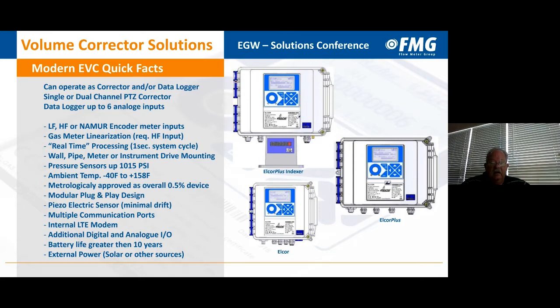Overall accuracy with the chart recorders, you were lucky to get 2% accuracy. Now you're looking at 0.5% accuracy, just using the electronics and doing real-time reads. In some of the older chart recorders, and yes, I'm guilty of selling some of them, I won't mention any manufacturers' names, but I sold a manufacturer that was only good to -10 degrees Fahrenheit. Today's electronic instruments, this one included, can handle an ambient temperature of -40 to +158.